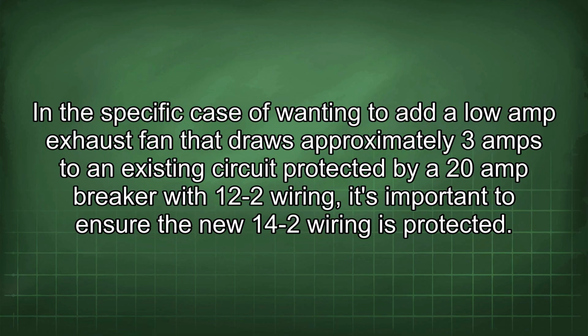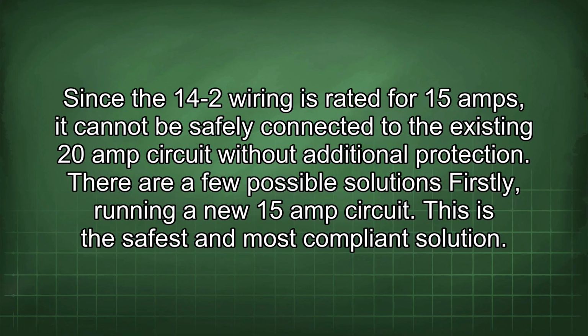In the specific case of wanting to add a low-amp exhaust fan that draws approximately 3 amps to an existing circuit protected by a 20-amp breaker with 12-2 wiring, it's important to ensure the new 14-2 wiring is protected. Since the 14-2 wiring is rated for 15 amps, it cannot be safely connected to the existing 20-amp circuit without additional protection. There are a few possible solutions. Firstly, running a new 15-amp circuit.